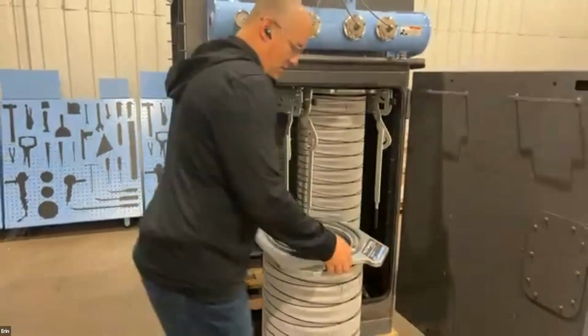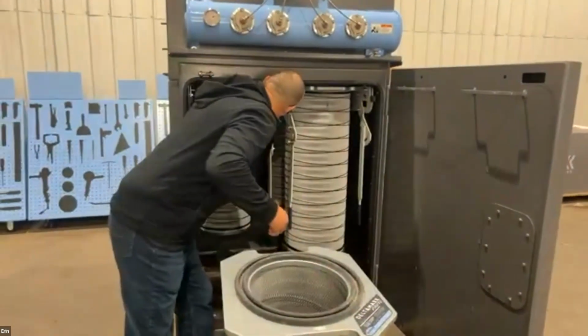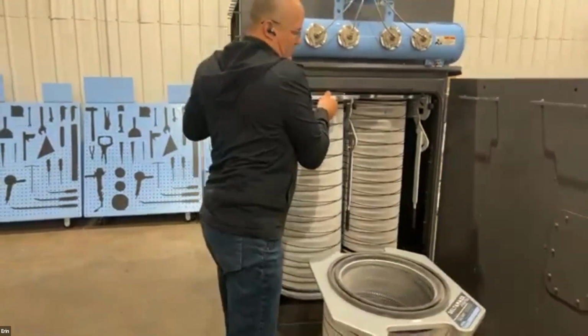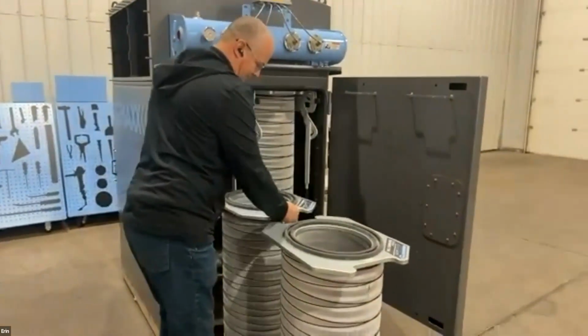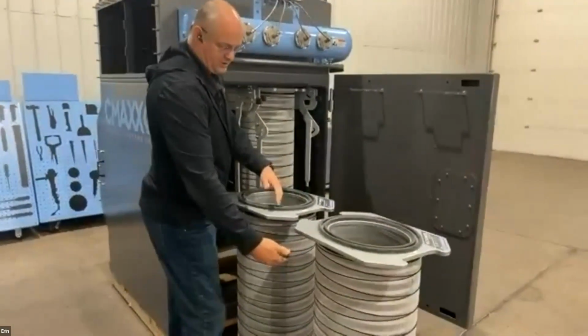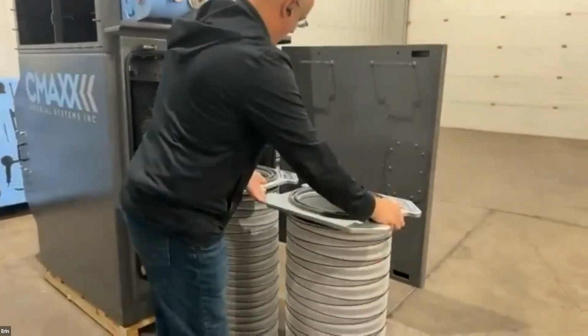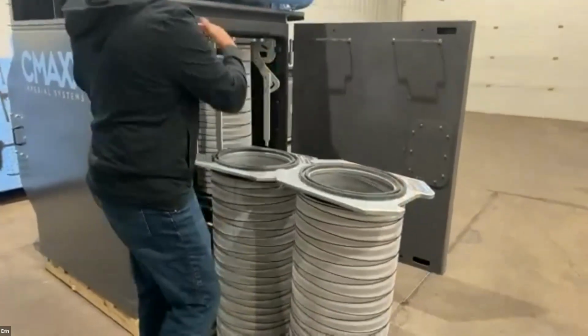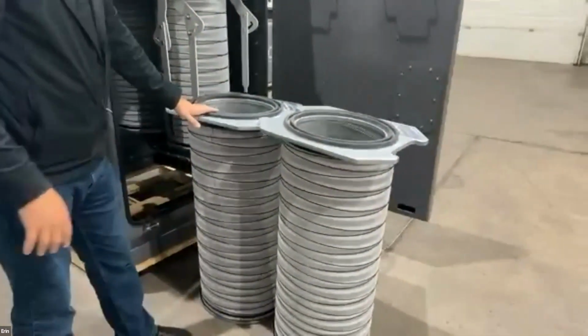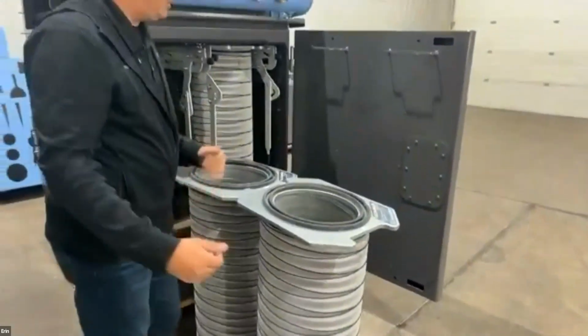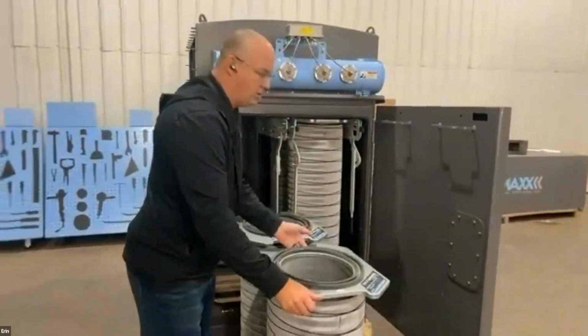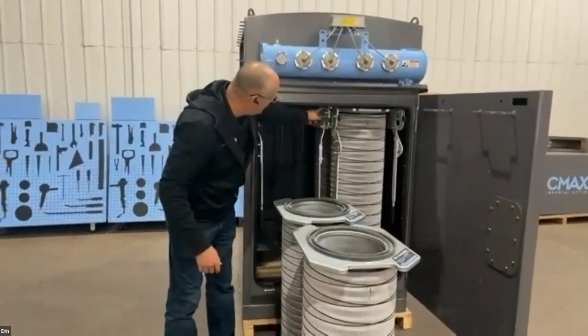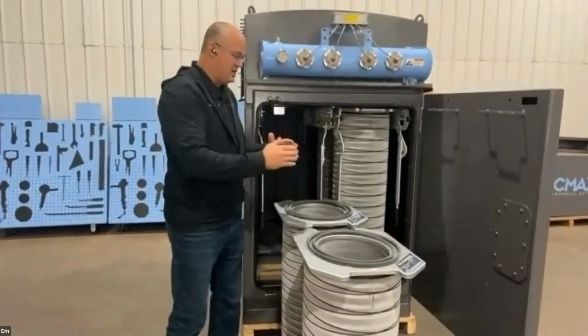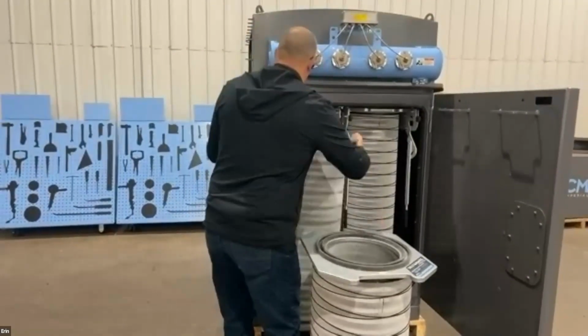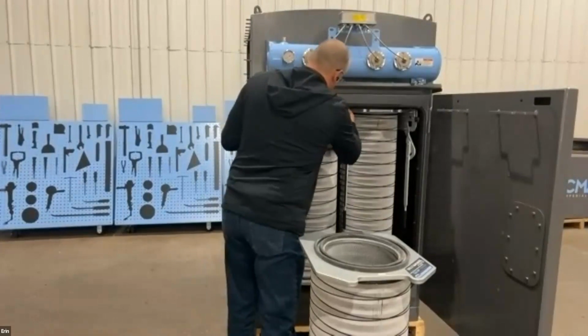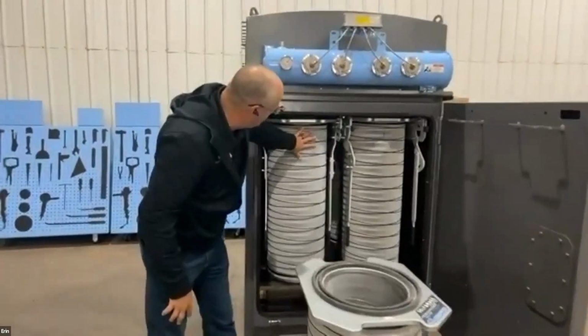A lot of times in this style of collector, I'm actually going to pull the other filter out to show you what can happen. When you are loading these filters, as someone loads this one, if they tend to push on the bottom of this filter, it can get set on top of the other filter in the collector. So there are other styles of collectors out there where that could be an issue. With ours, we have the ability to add a top channel onto this, which prevents that from happening, because there's just enough room for the filter to go in.